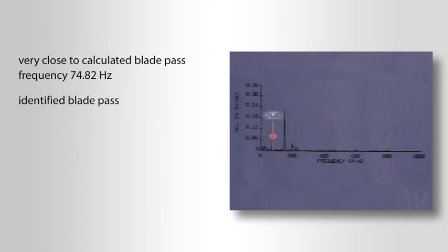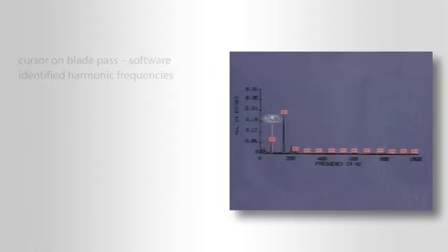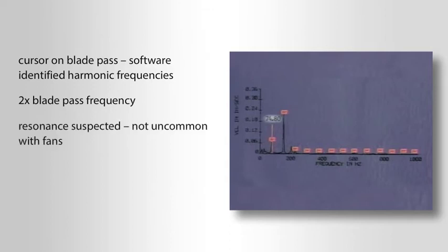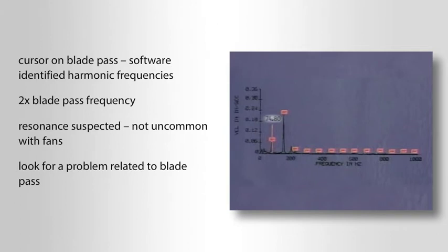So far, a low-amplitude one-times and a blade pass frequency are very much what we would expect to find — that is step five. But when we place the cursor on the blade pass, the software identified harmonic frequencies with a high-amplitude peak at two times the blade pass frequency. Because the blade pass harmonics could not be readily explained, resonance was suspected. Resonance is not uncommon with fans, but let's not draw conclusions yet. For now, let's continue to look for a problem somehow related to blade pass.